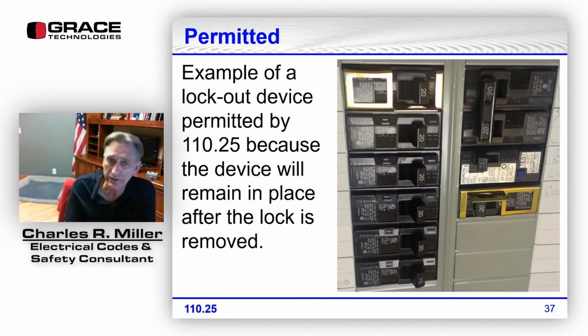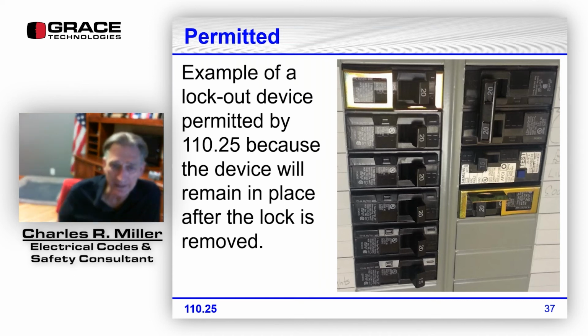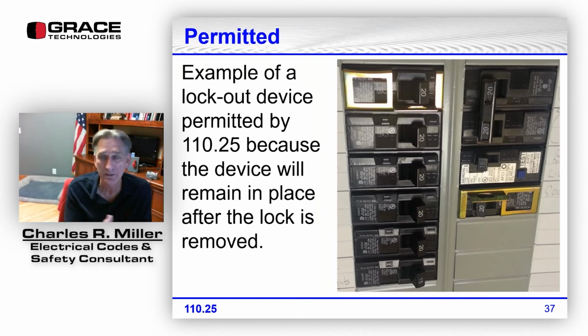When this was first put in Article 110.25, the wording that first went in there for one edition says the device has to be permanent. Well, that's really not what the committee meant, and they remedied it with the next edition. These devices, these little brass devices here, you take the panel cover off, you can pull that device off, put it back on, and so technically they're not permanent. Well, the committee didn't mean it had to be permanent, so they changed the wording to what we have now, and it says it has to remain in place with or without the lock installed.